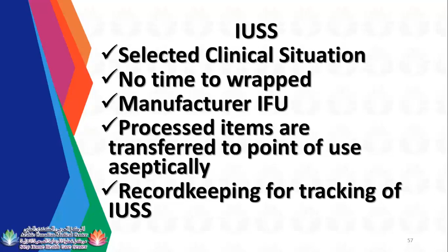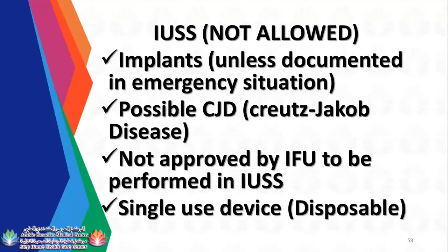Possible CJD, or Creutzfeldt-Jakob disease: if it is possible CJD, then IUSS is not allowed. In CJD, you need to soak your instruments in sodium hypochlorite and sterilize as per CDC guidelines before you can do the routine sterilization process. Not approved by IFU to be performed in IUSS: as I said a while ago, you are only allowed to perform IUSS if it is written in your IFU. If it is not written in your IFU, then you are not allowed to perform IUSS. A single-use device should not be processed in IUSS. Okay.